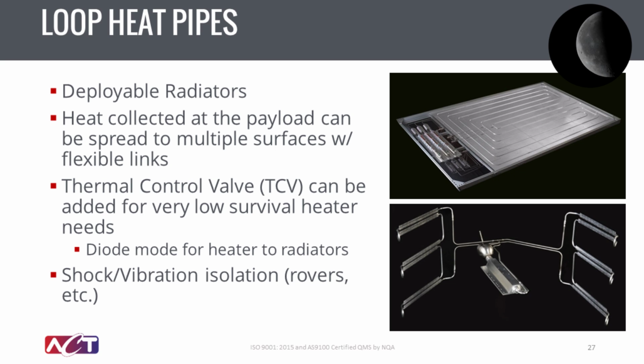One of the additional benefits of a loop heat pipe is that it can go into diode mode as well. So if there is heat applied to the radiators that is greater than the temperature of the evaporator where the pump body is, that will prevent backflow of heat into your warm box. And one of the things that is also nice is that these can be designed to provide shock and vibration isolation for rovers.